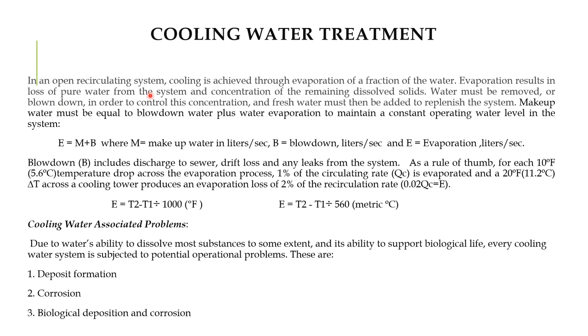In an open recirculating system, cooling is achieved through evaporation of a fraction of the water when it is distributed through distributor nozzles. This evaporation results in loss of pure water and concentration of dissolved solids (TDS) in the cold basin. Water must be blown down to control TDS concentration, and makeup water must be added to replenish the system. Makeup water equals blowdown plus evaporated water to maintain a constant operating level.